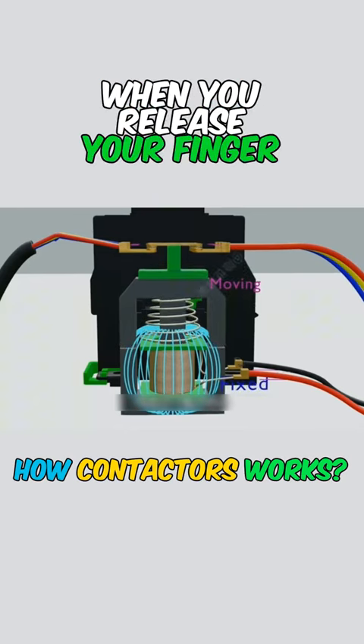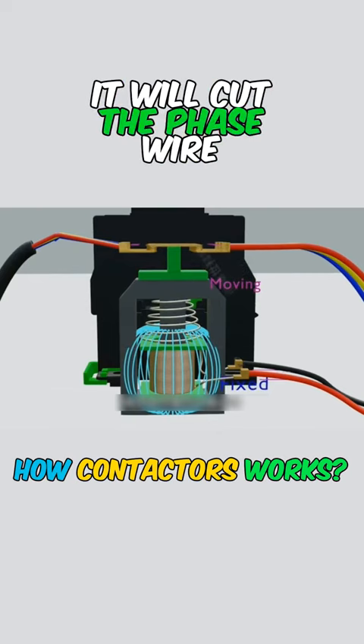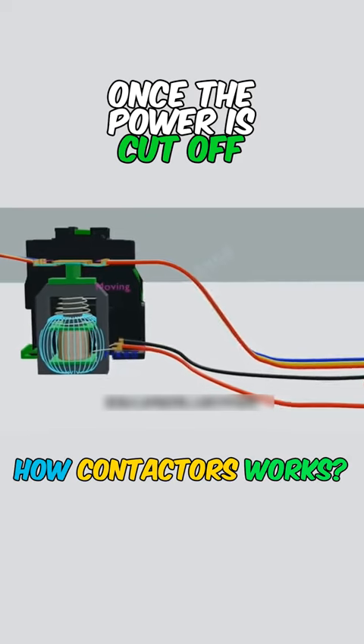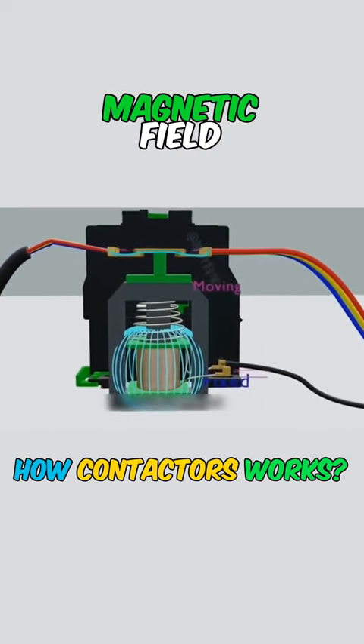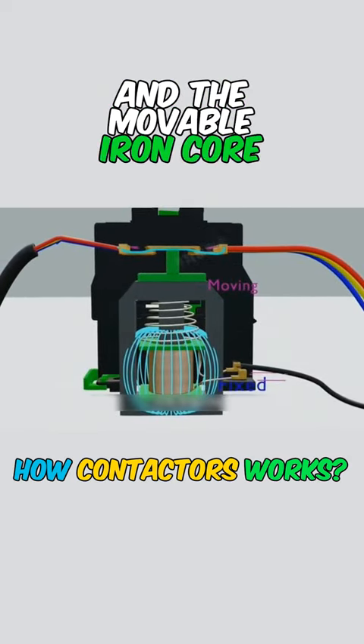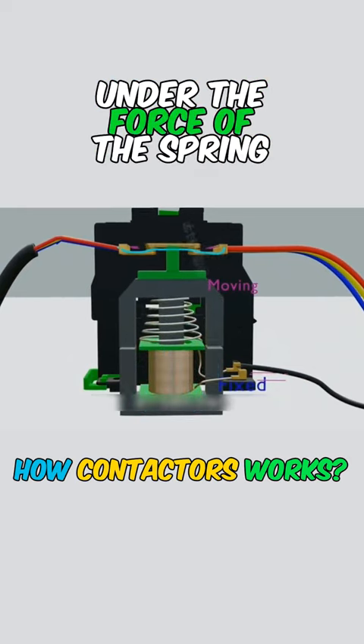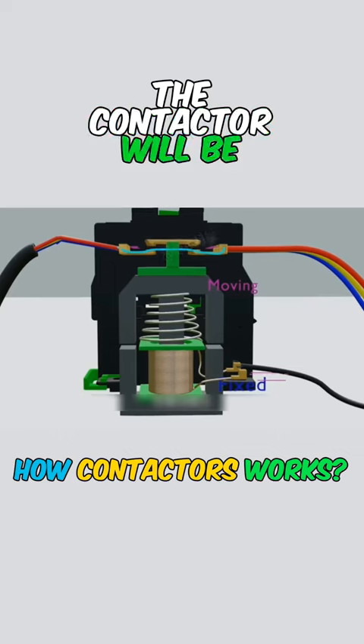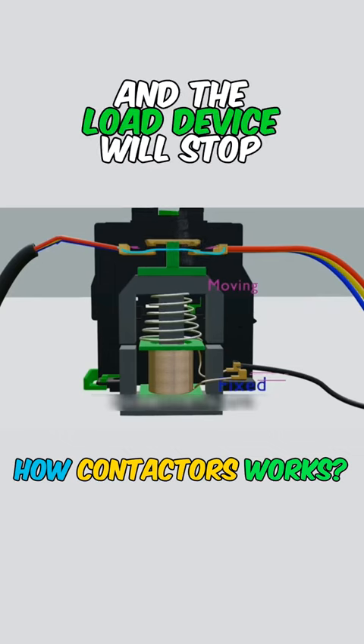When you release your finger from the start button, it will cut the phase wire. Once the power is cut off, the coil will lose its magnetic field and the movable iron core will move upwards under the force of the spring. The contactor will be detached and the load device will stop running.